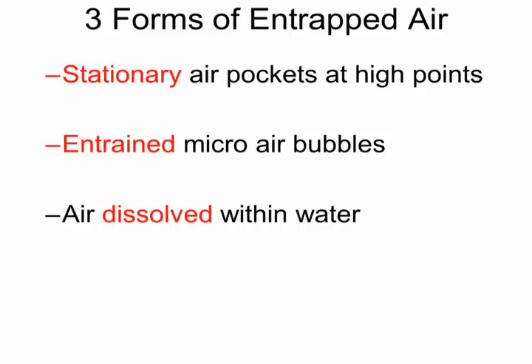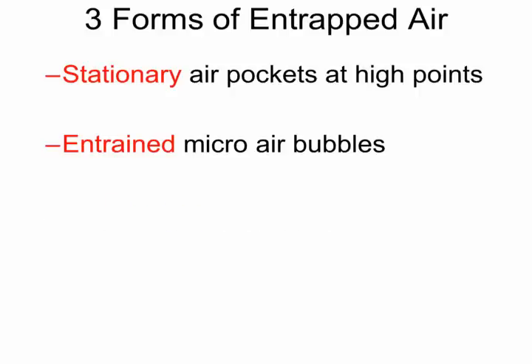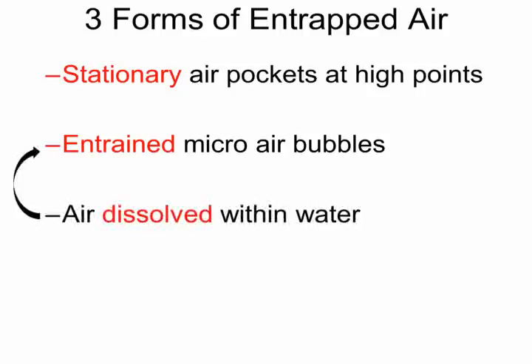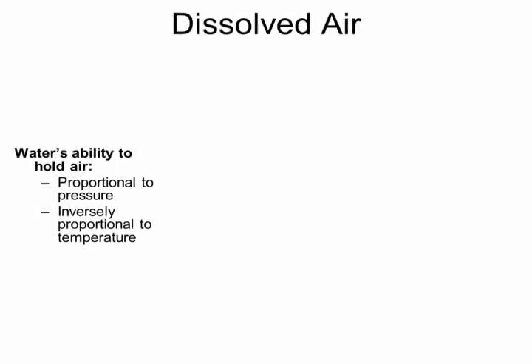Now, as it relates to the efficiency of the pumps, we don't care if air is dissolved. If it stays dissolved, we don't really care. Water is incompressible. The problem is as water undergoes pressure changes and temperature changes, it will come out of solution, and it will end up as a microbubble, and those microbubbles will accumulate and end up as air pockets. That's kind of the migration of what happens in a system.